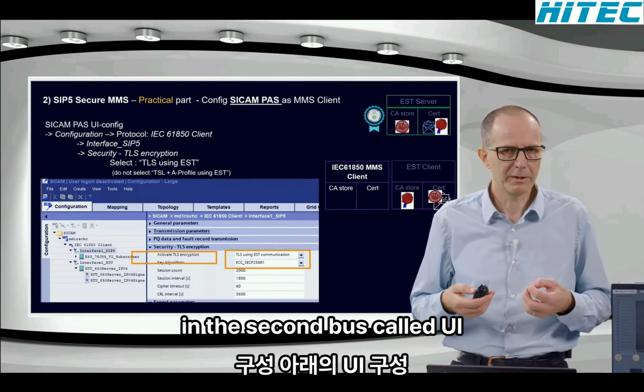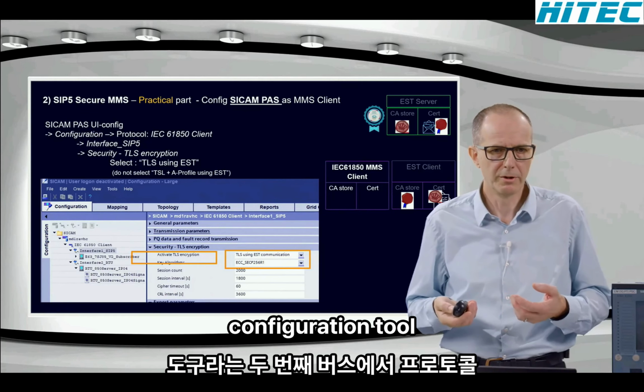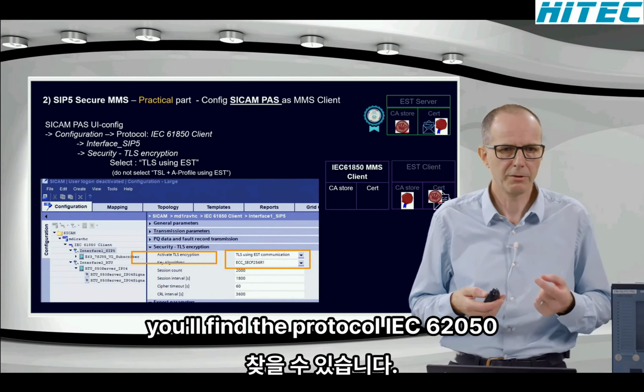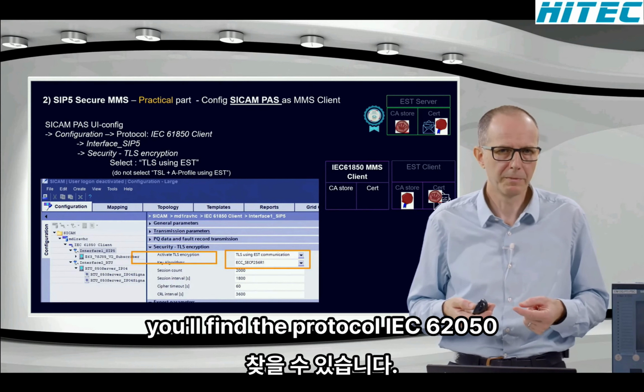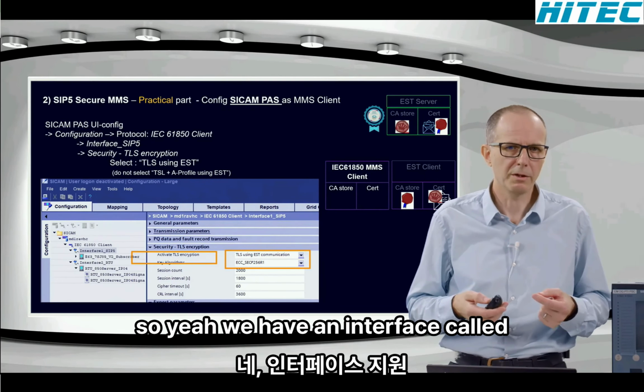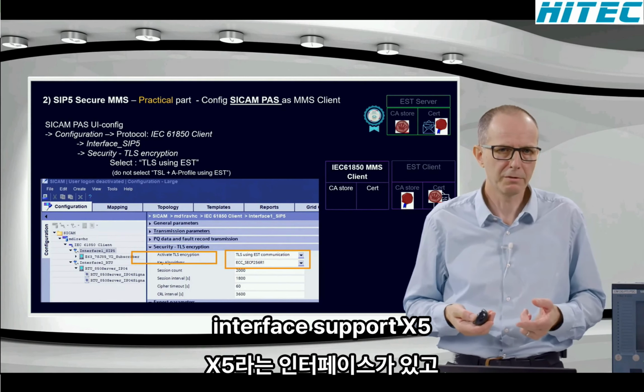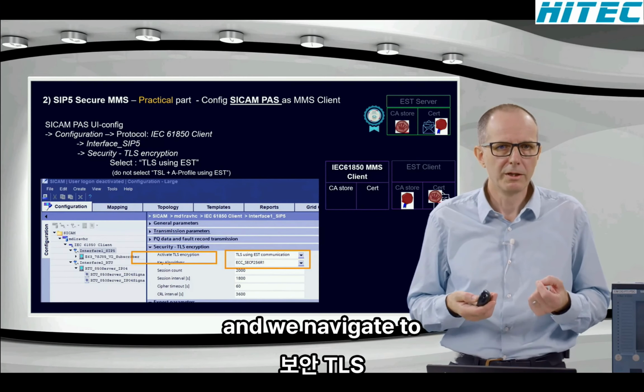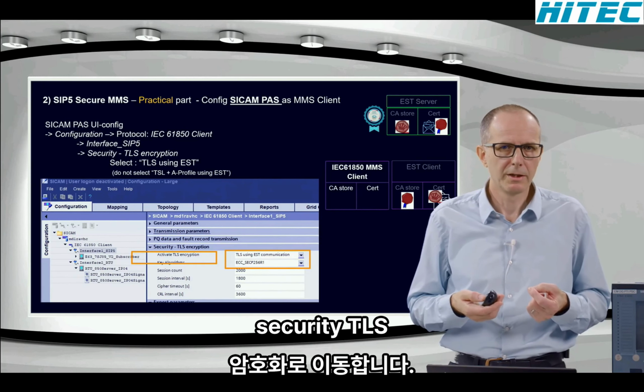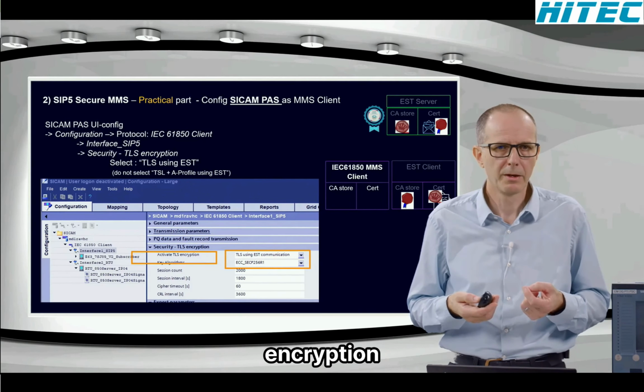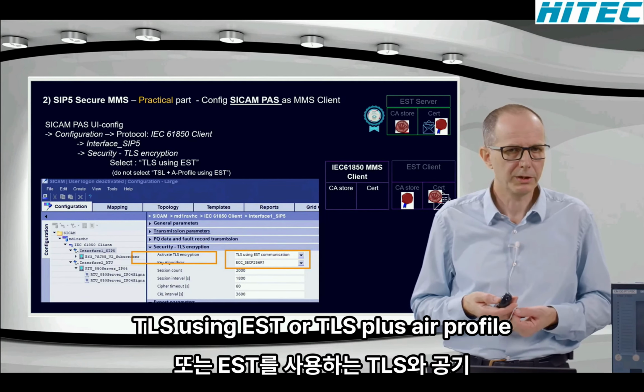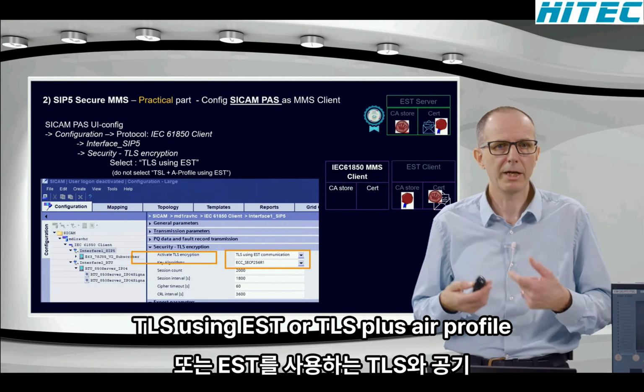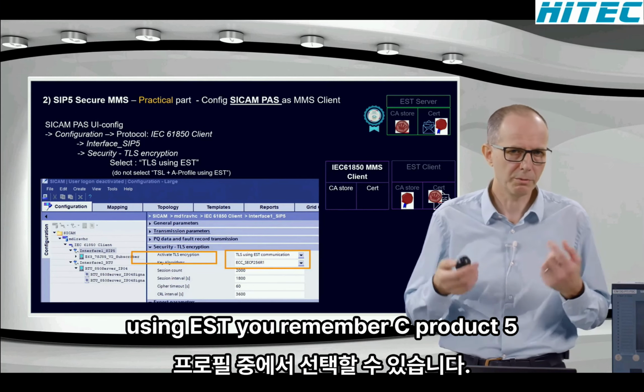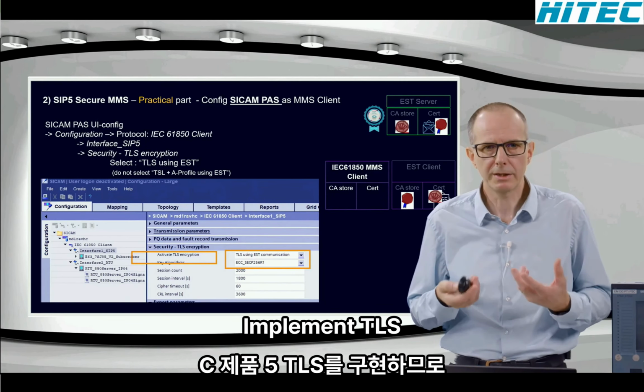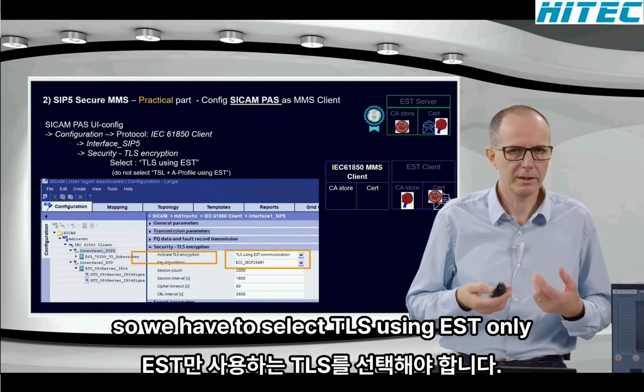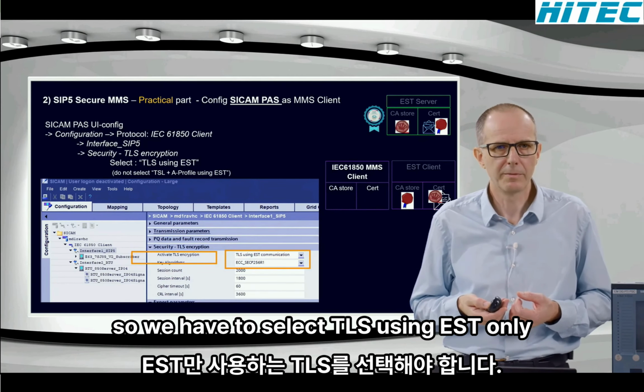In the SICAM PAS configuration tool, under configuration, you find the protocol IEC 61850. There we have an interface called interface SIPROTEC 5, and we navigate to security TLS encryption. We can select between TLS using EST or TLS plus a profile using EST. You remember, SIPROTEC 5 implements TLS, so we have to select TLS using EST only.